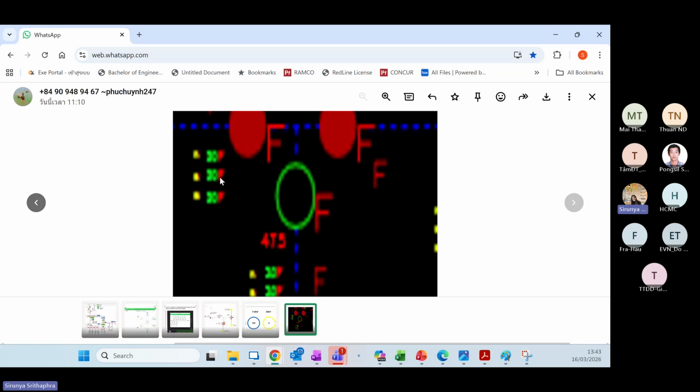Any suspect data means that, for example, after 10 seconds they send a GI command to the RTU. If they send back all of those signals and the SCADA system receives them with good quality, the F is hidden.